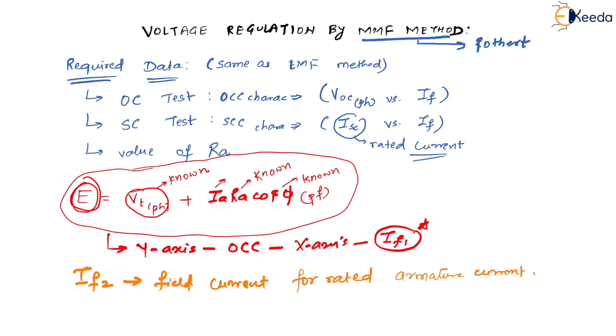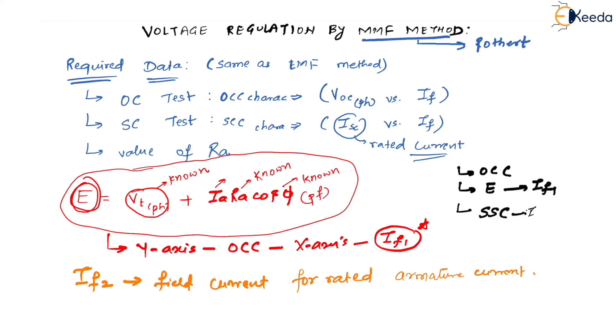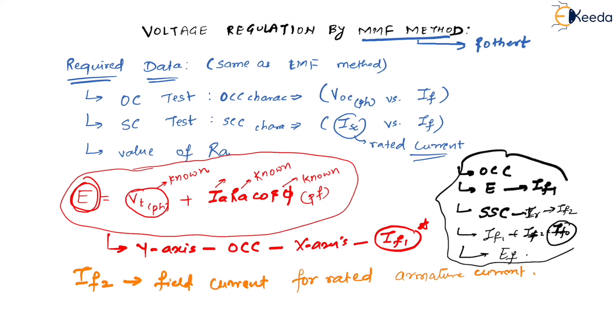Let us revise the steps: Step 1 — find and plot OCC. Step 2 — find E = VT + IA·RA·cos φ. Step 3 — from E, find IF1 on OCC. Step 4 — plot SCC and from rated current find IF2. Step 5 — add IF1 and IF2 as phasors to get IF0. Step 6 — locate IF0 on OCC to get EF. This is the complete procedure. We will solve numerical examples in the next session.